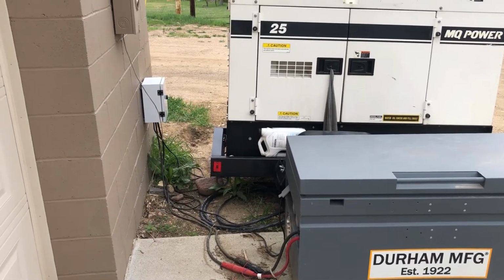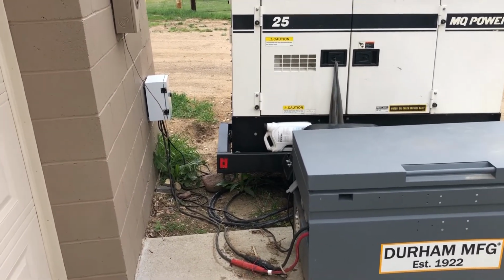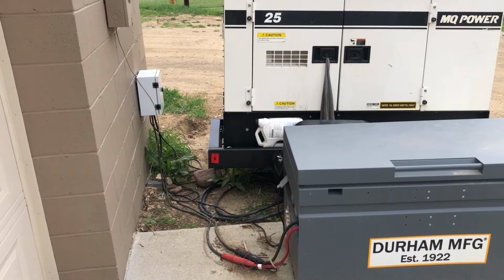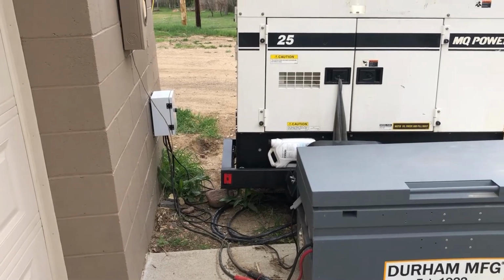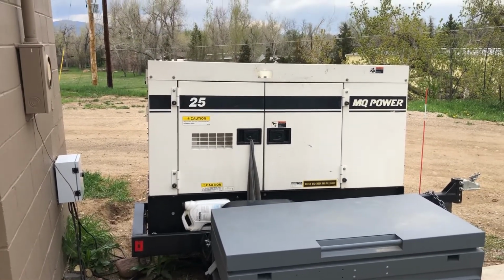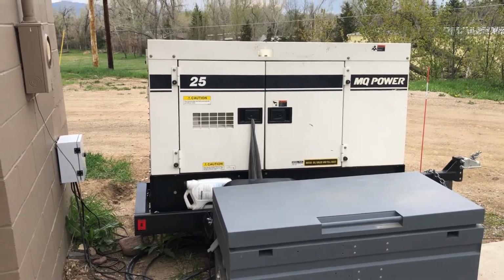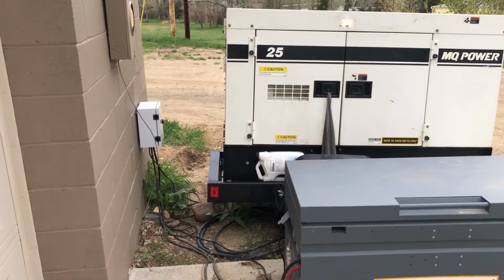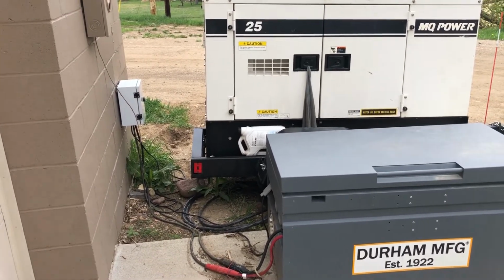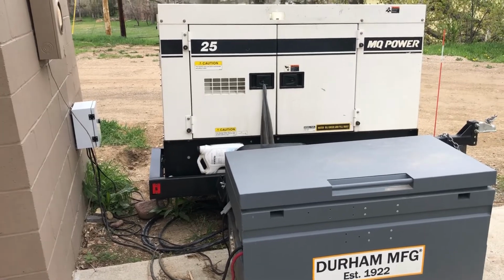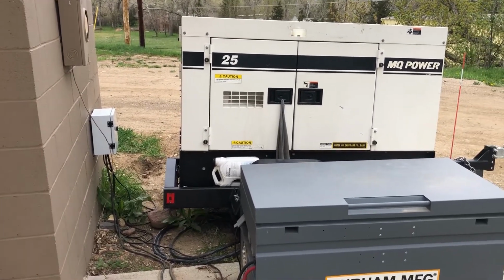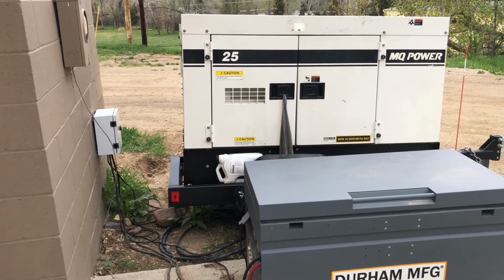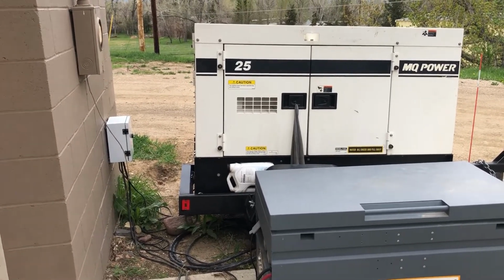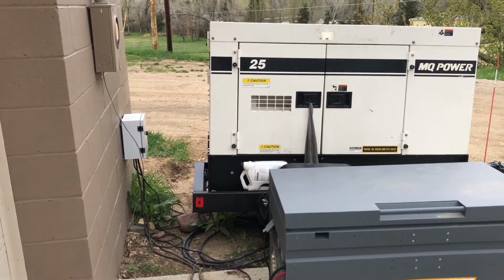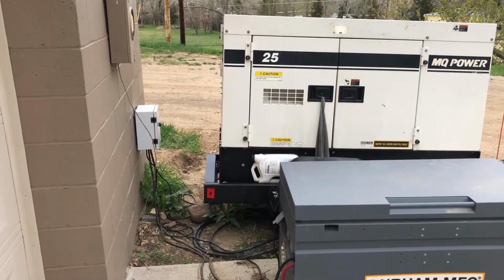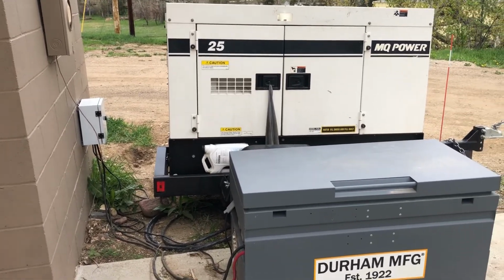that disaster, and the owner had been negotiating with the county government to reestablish their electrical service for that time in hopes while running this diesel generator, and that just didn't work out. So I really wanted to shut down the diesel generator, so I adapted some stuff that I had laying around, and this is a little tour of that installation, which has been running for about 3 months now successfully. We had 2 separate overload events where the inverter shut down due to AC overload on one of the 2 phases, but besides that it's been running pretty good.